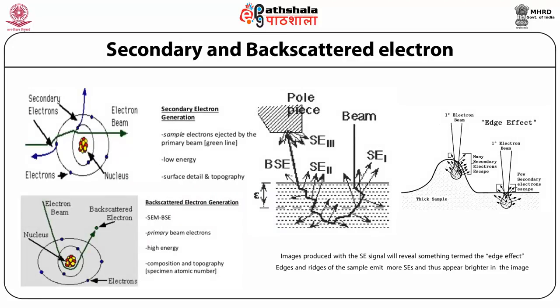In this slide we discuss about secondary and backscattered electrons and how they form. When the incident beam enters the specimen, secondary electrons are produced from the emission of valence electrons of constituent atoms in the specimen. Since the energy of secondary electrons is very small, those generated at deep regions are quickly absorbed by the specimen. Only those generated at the top surface are emitted outside. This means secondary electrons are very sensitive to the surface. The difference in brightness of the crystal surface is due to the difference in the incident angle of the electron beam. Thus, secondary electrons are used to observe the topography of the specimen surface.